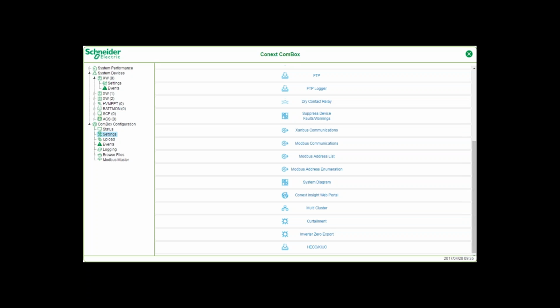You can also set up for Modbus communications in case you have external RS-485 devices that you want to add, which includes power meters, pyrometer for measuring temperature, and we also have the Conext Insight web portal data push for setting up for Insight. We'll talk more about that in a few.